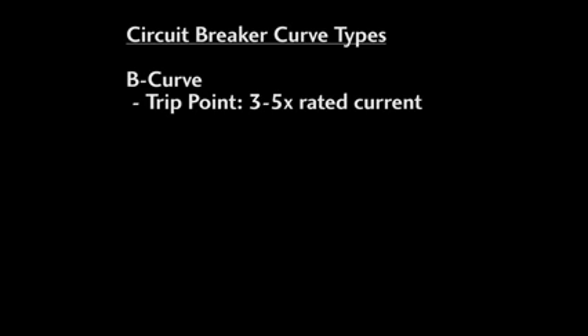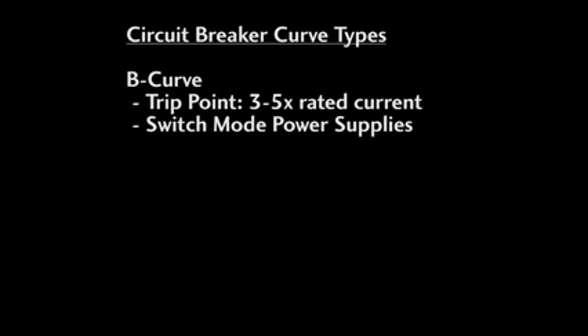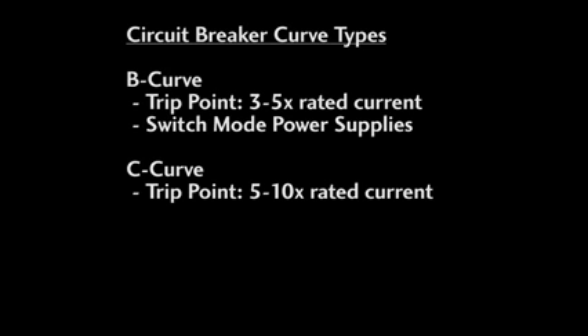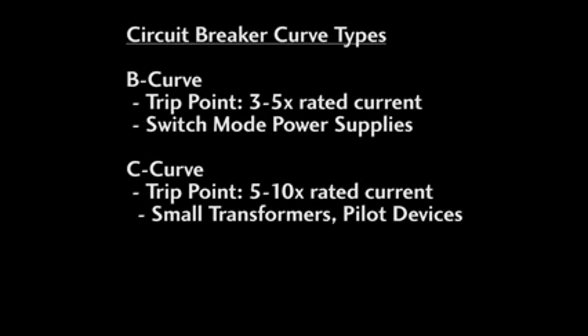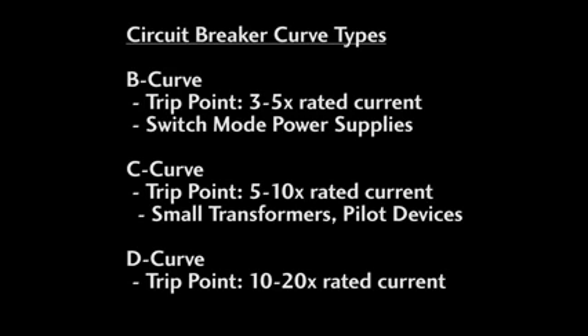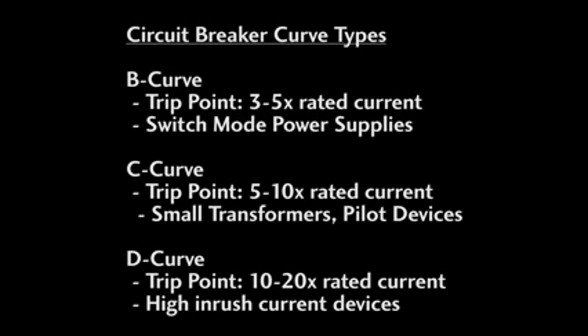Circuit breakers are rated using a curve type. A B curve type circuit breaker can handle 3 to 5 times the rated current before it trips. They're great for small switch mode power supplies where you need to be able to handle the inrush current, but need to be in a couple amp range while operating. The C curve has a trip point of 5 to 10 times the rated current. These are general purpose and great for small transformers and pilot devices. The D-type curve trips at 10 to 20 times the rated current. These are used for transformers or high inductive loads like motors that need time to get past the high inrush current without the circuit breaker tripping.